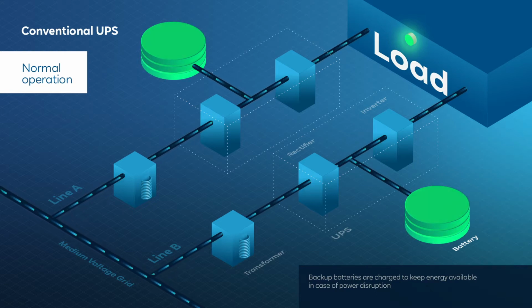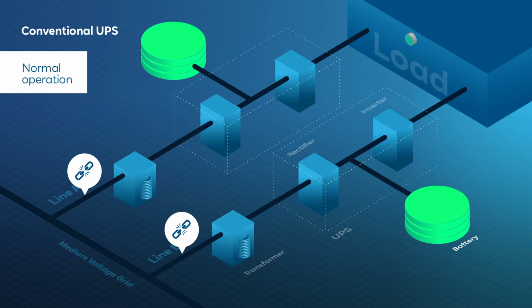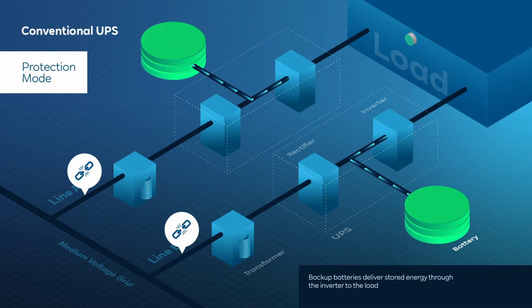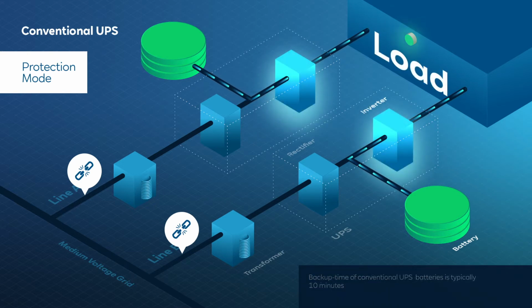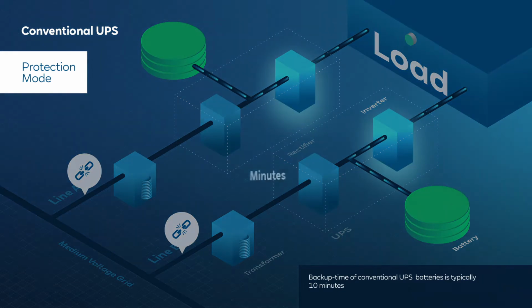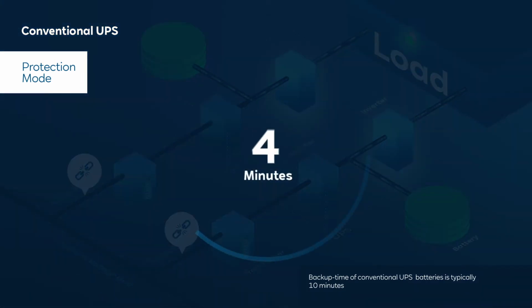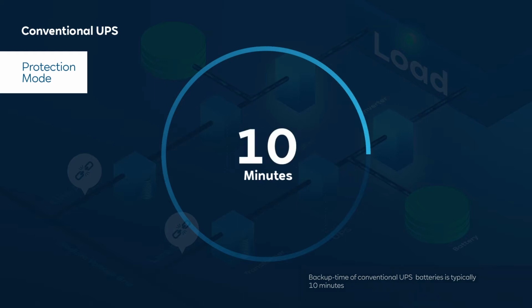power disruption. In case the power supply is in danger, the UPS system switches to protection mode, instantaneously supplying the energy stored in the batteries through the inverter to the load. The backup time is long enough to start a standby power source, for example, emergency engine, which gives time to the grid to restore normal operating conditions.